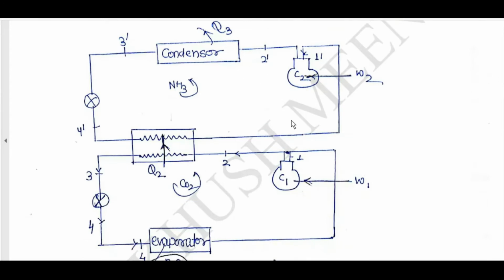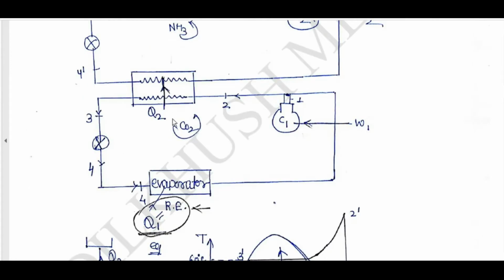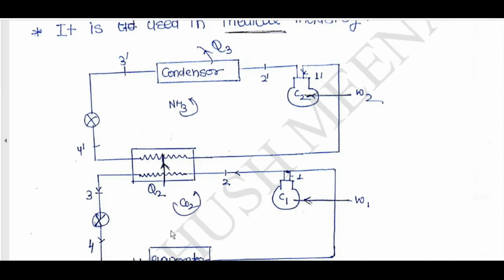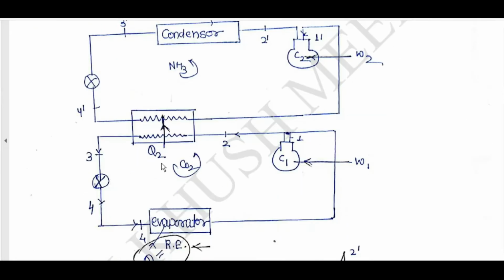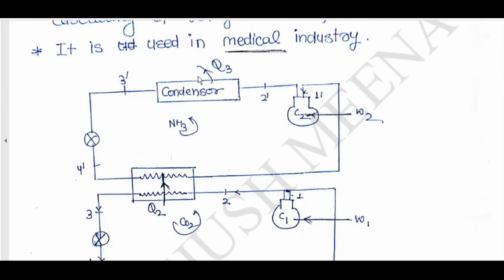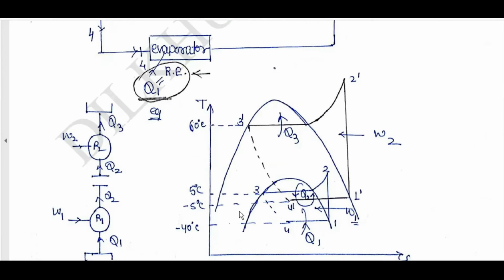In the condenser, NH3 will be moving, and CO2 will be moving in here. Compressor, Q2, evaporator. Q1 is the refrigeration effect. Q2 from this refrigeration cycle will be used for the evaporator in the NH3 cycle. Condenser Q3 will be released out.